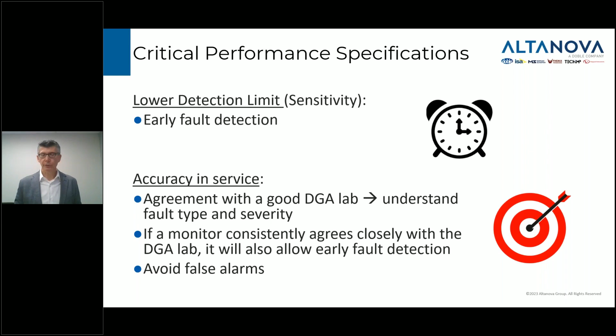The other big advantage to having an accurate monitor is to avoid false alarms. False alarms can be very effective at eroding people's confidence in the DGA monitoring program. People on the maintenance team who go out chasing false alarms can get frustrated by that, and management can lose confidence that it's a good investment to have the teams doing that. So a really important feature of a good monitor is that it does not generate false alarms, but rather continues to deliver accurate readings throughout the year.